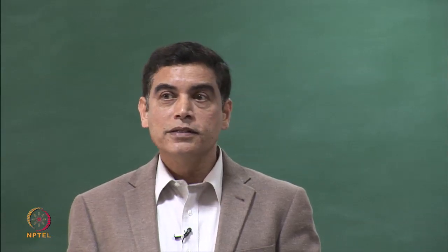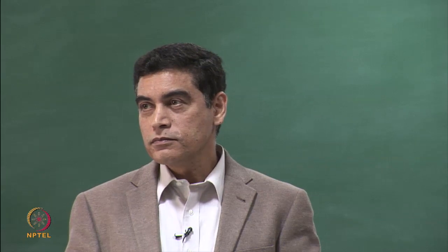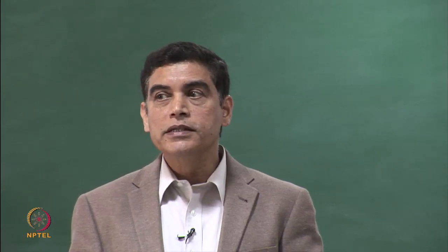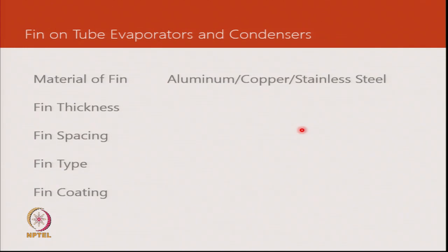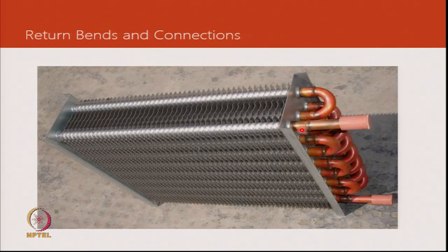Uniform air distribution is an ideal — it never really happens in real life. We try to maximise the evenness, and the rest is taken care of by circuiting. The top and bottom of the evaporator are usually starved of air due to insulation, covers, or drain pan components. One design approach is to add additional tubes in the top and bottom circuits and equalise the circuiting in the rest, assuming air flow in the centre of the heat exchanger will be even.